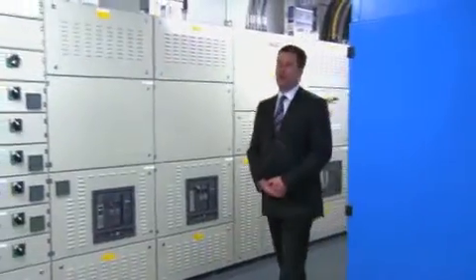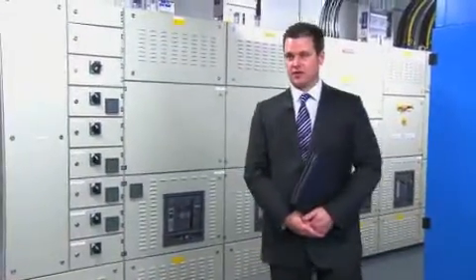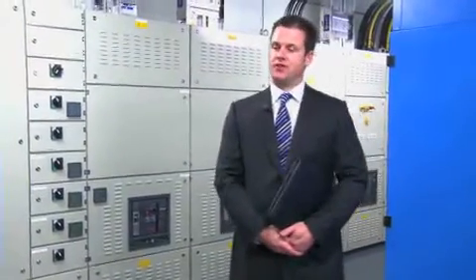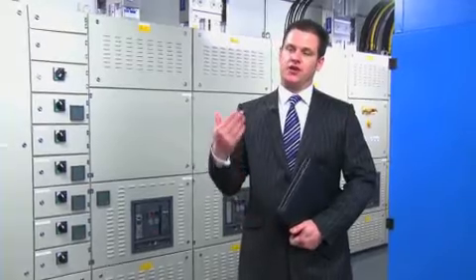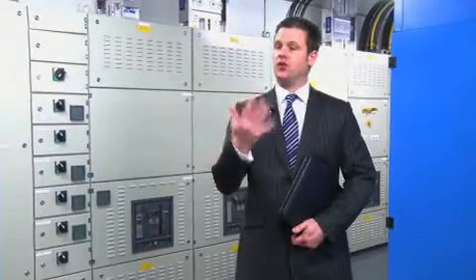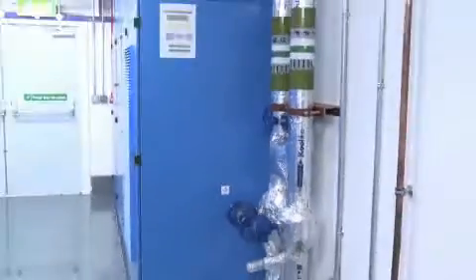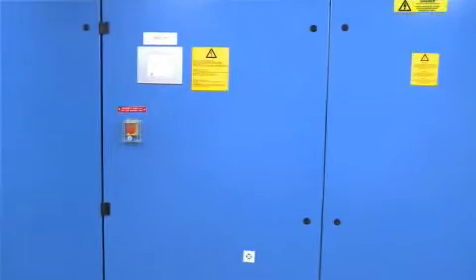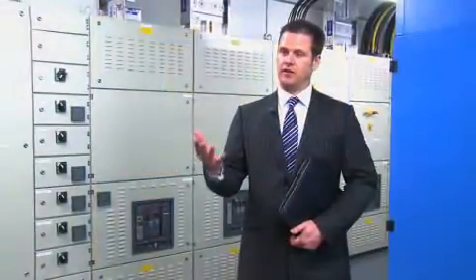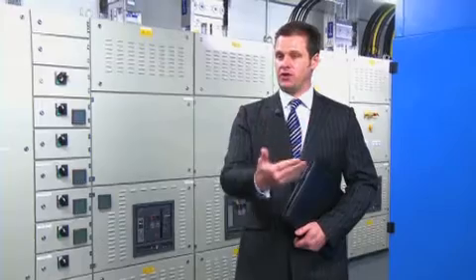So this is one of our 12 UPS rooms. Each room has 4 hybrid UPS units configured in an N+1 basis. These units provide the conditioned power to the data suites. Should there be a mains fluctuation or outage, the units are backed up for 10 minutes by battery. It only takes a matter of seconds for the generators to come up to speed. Once they're at speed, the units are then powered by the generators.